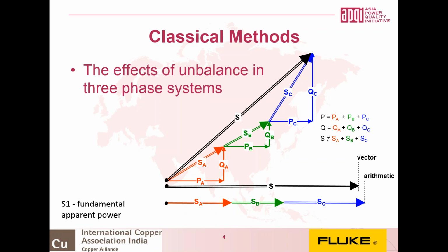Because if we think about the powers and the reactive powers, they're always pointing in the same direction and can be added simply, so the magnitude doesn't change. But because the apparent power has a direction too, depending upon the phase angle or power factor in the system, that can affect the magnitude in terms of the overall capability of that power. So we have a situation where potentially we're overstating the apparent power, which can cause cost implications, and the likelihood that we overinvest or underinvest, when we want to keep the electrical network as healthy and as efficient as possible for the right amount of money, of course.